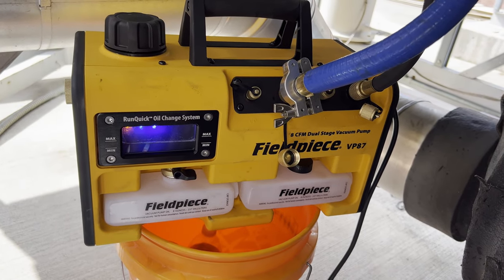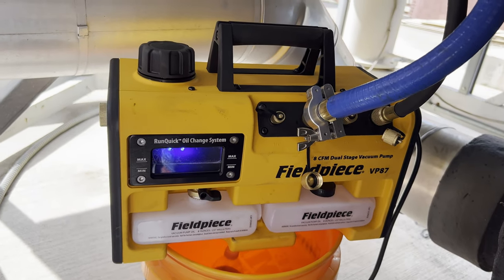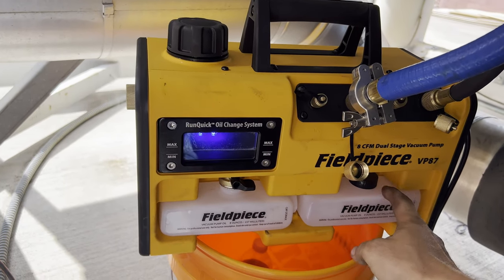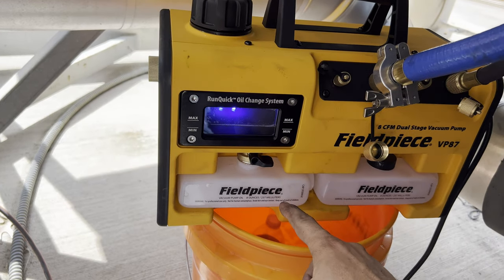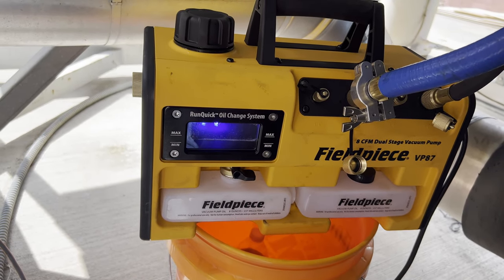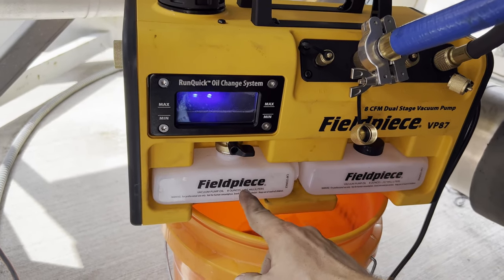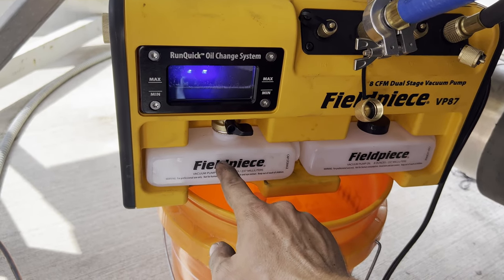For those of you that aren't aware how the RunQuick oil change system works: basically the Fieldpiece pump can run for 30 seconds or so after you drain the oil. So that's what you have the spare oil container for. If you need to change the oil in the middle or towards the end of your vacuum process, you leave the pump running and open this valve right here — that's going to dump all of your existing oil into this container.